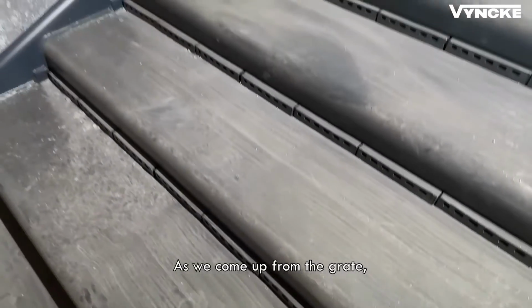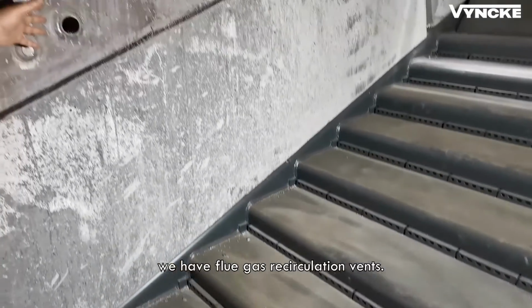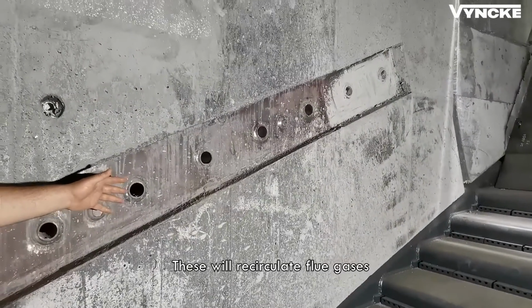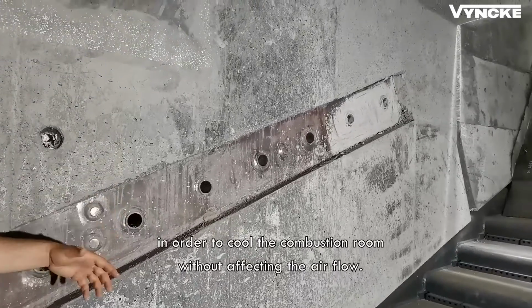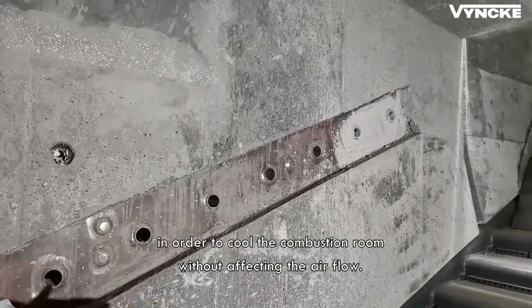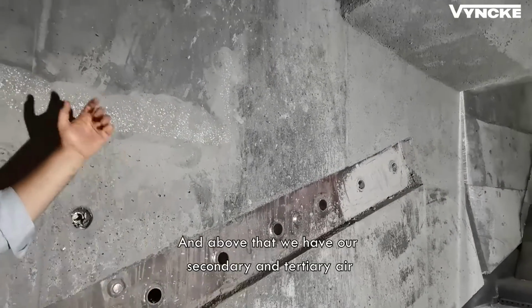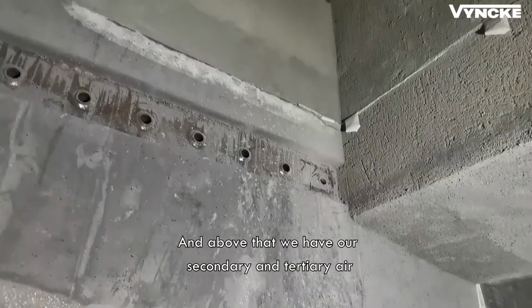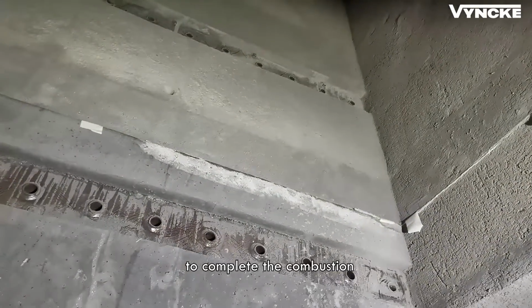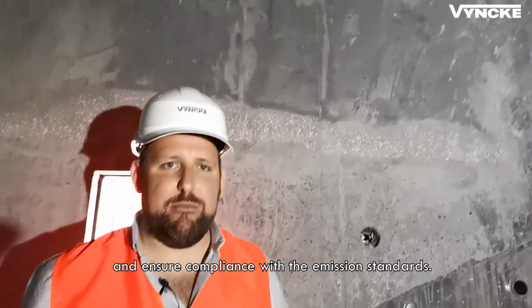As we come up from the grate, we have flue gas recirculation vents. These will recirculate flue gases in order to cool the combustion room without affecting the airflow. And above that, we have our secondary and tertiary air to complete the combustion and ensure compliance with the emission standards.